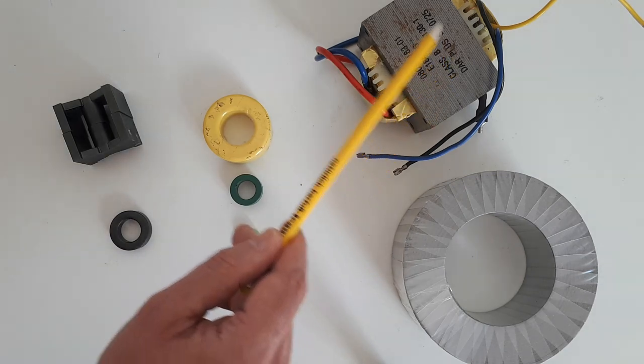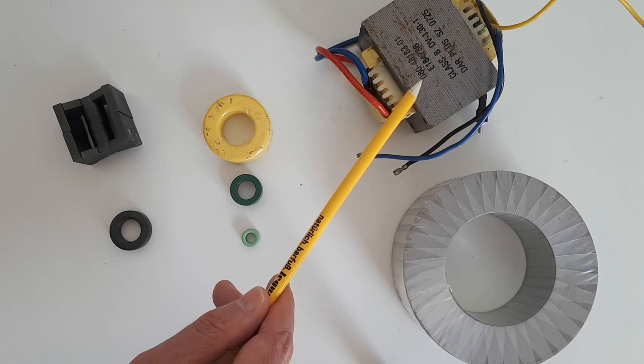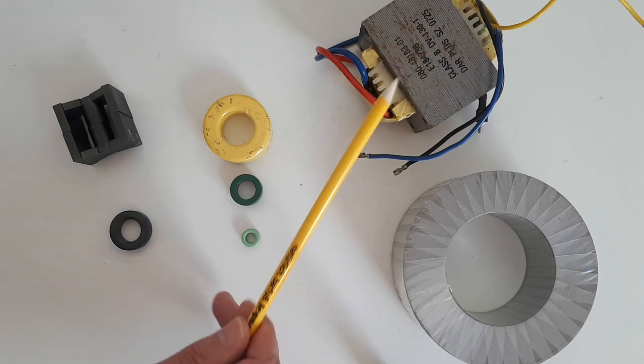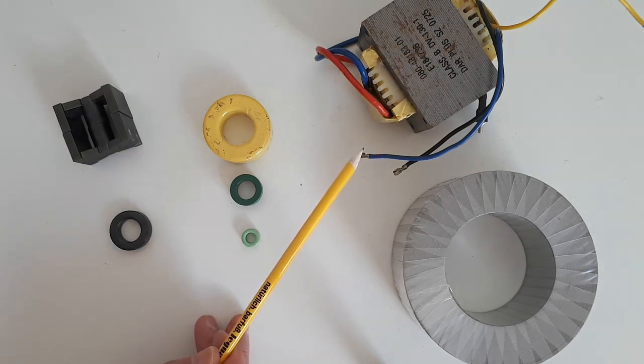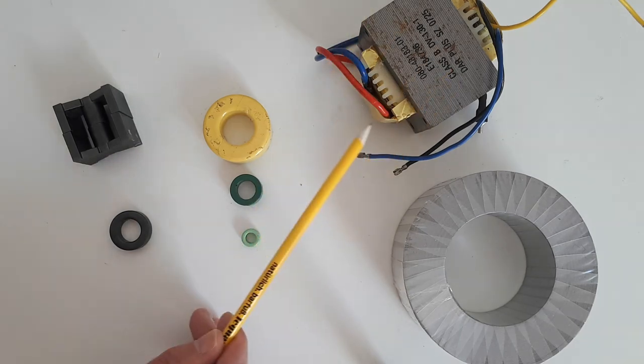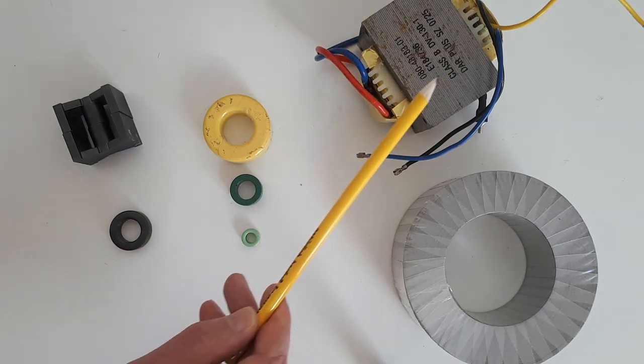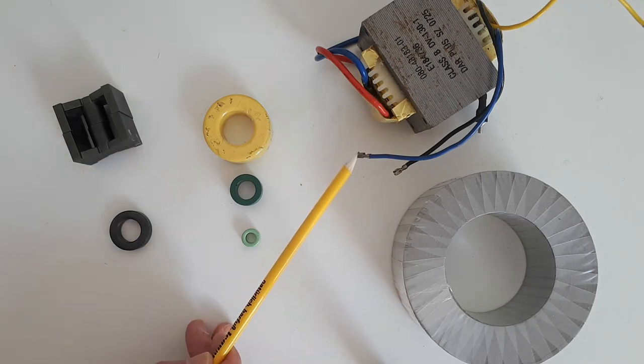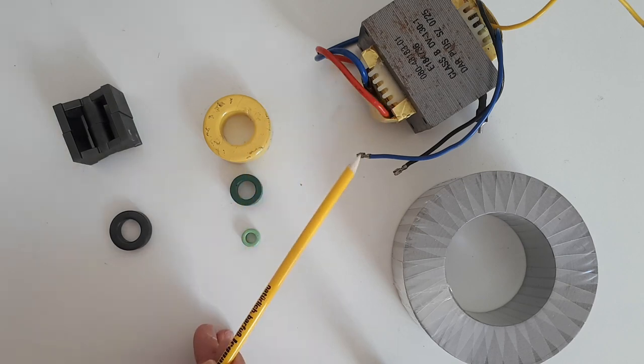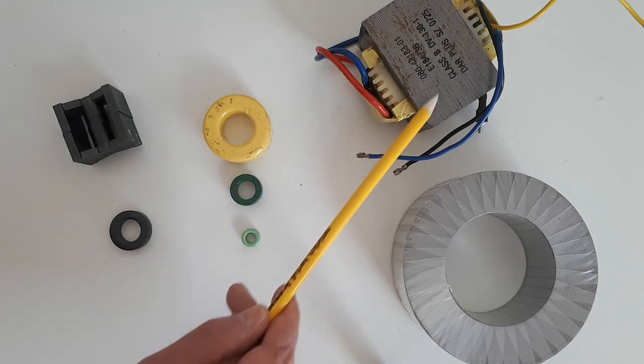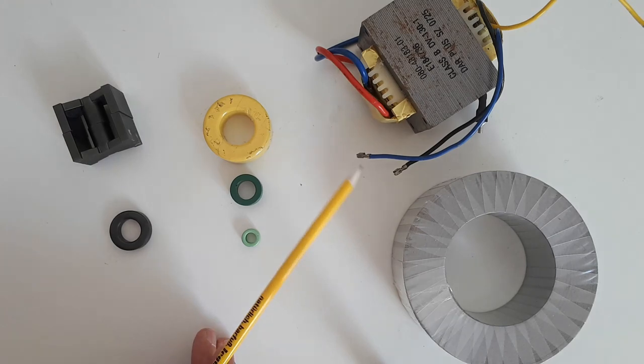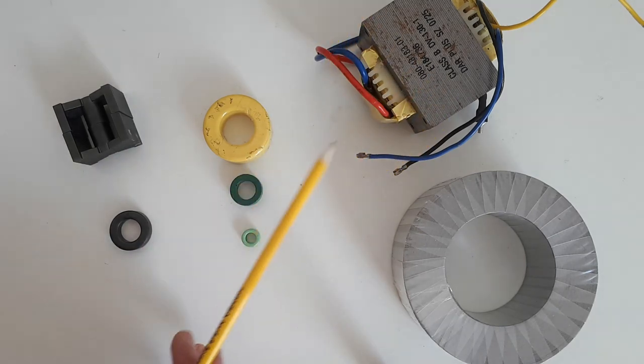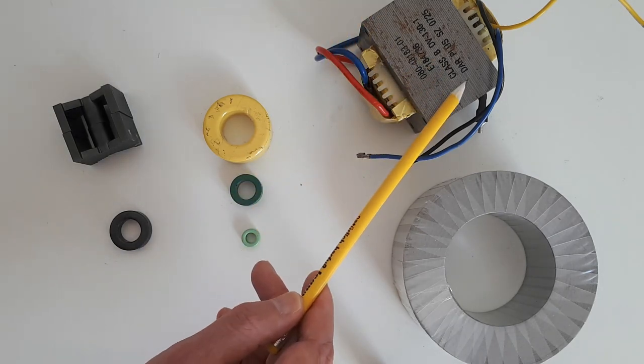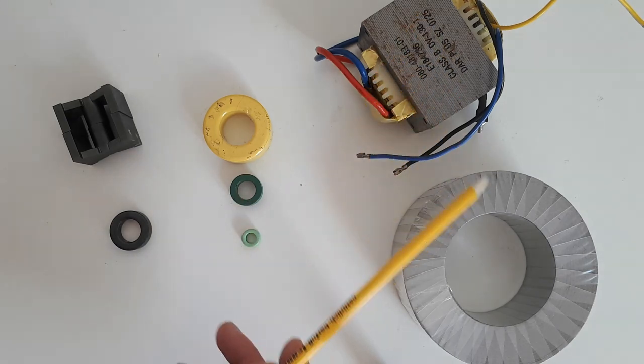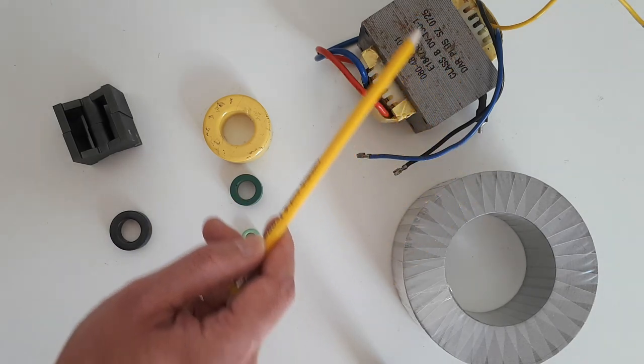Eddy currents are produced because the magnetic field of the transformer is, of course, changing in time, and that creates induction in the metal. And the direction of those eddy currents are in a direction such that they produce a flux which is in opposition to the flux which you're trying to create, and in general they create a lot of loss in the material. And in order to cut down on those losses and therefore heat, the iron core is divided into laminations.